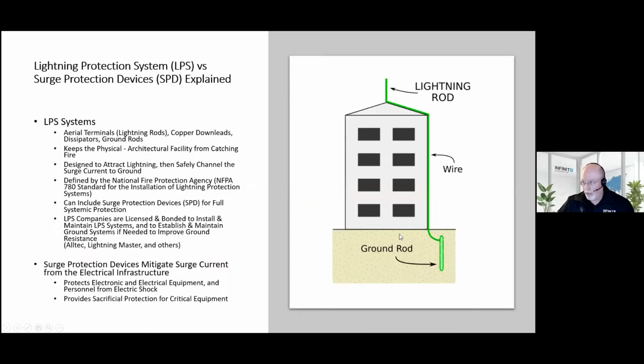So there's some confusion sometimes. People don't know the differences, but somebody will call and say, I need a lightning protection system. And so I just want to qualify with what that means. And that is referring to lightning rods, ground rods, and the down lead conductors here that connect them. This is designed to protect the architectural building from catching on fire.